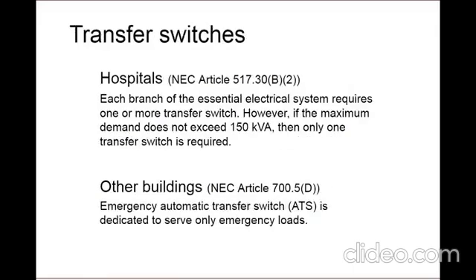There is also a difference with the transfer switches allowed in NEC 517 that is not permitted in NEC 700. Emergency automatic transfer switches under Article 700 are only permitted to serve emergency loads. Article 517 allows the designer to combine up to all three branches of the essential electrical system under one automatic transfer switch if the maximum demand does not exceed 150 kVA.